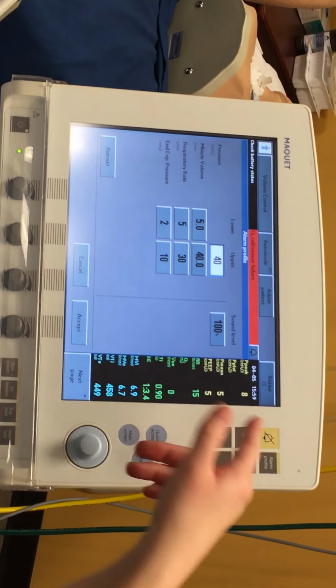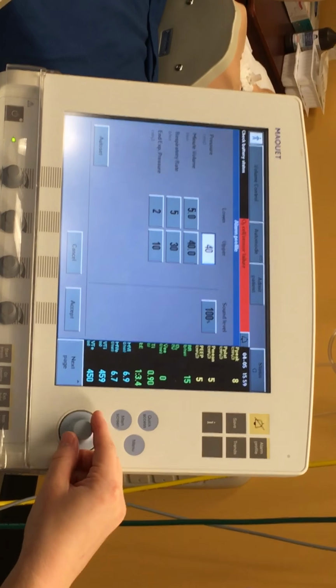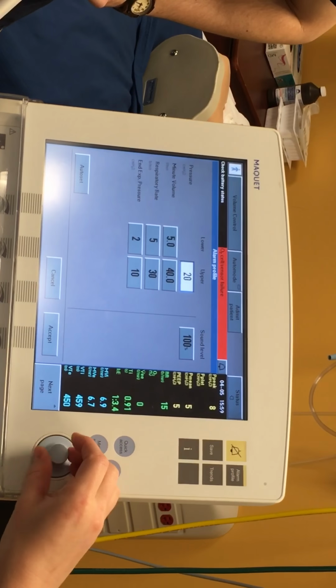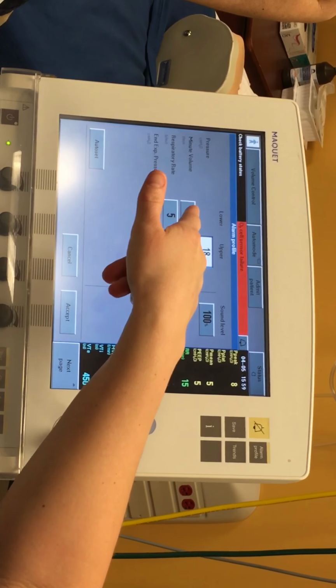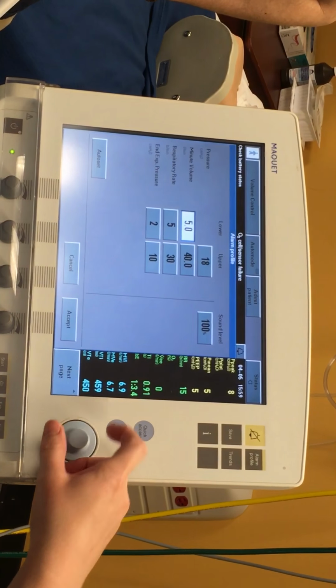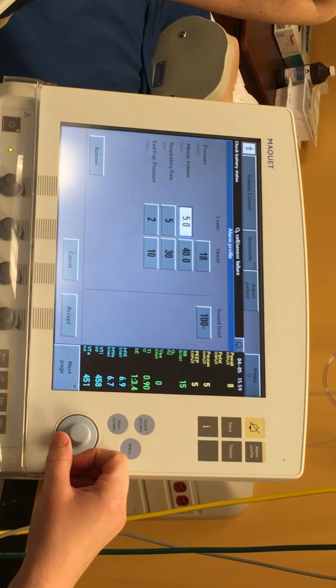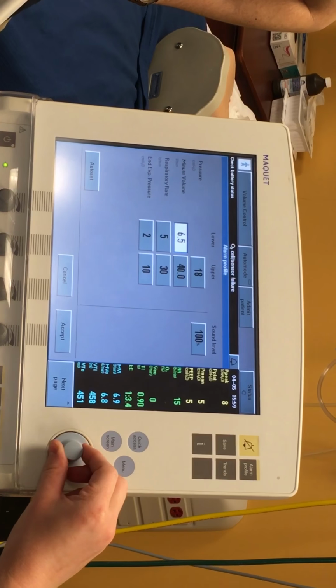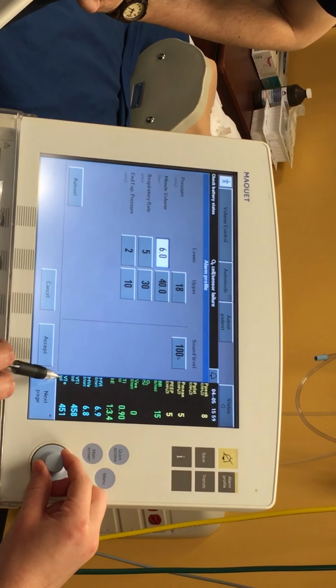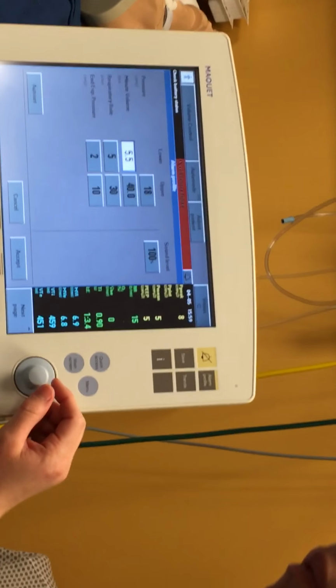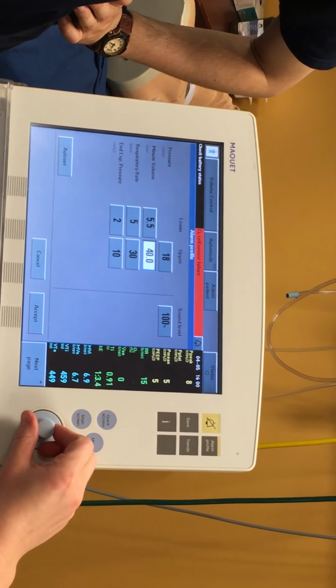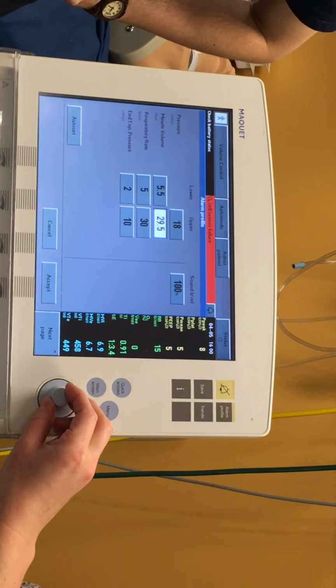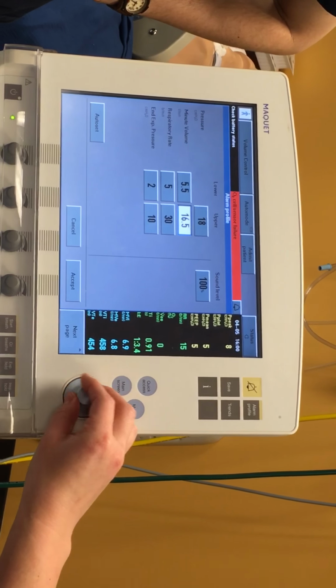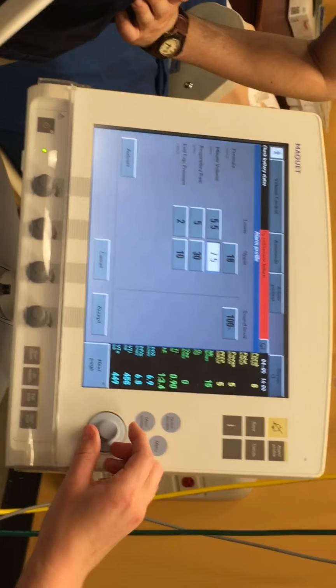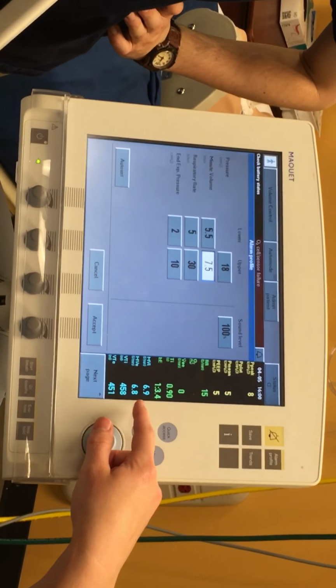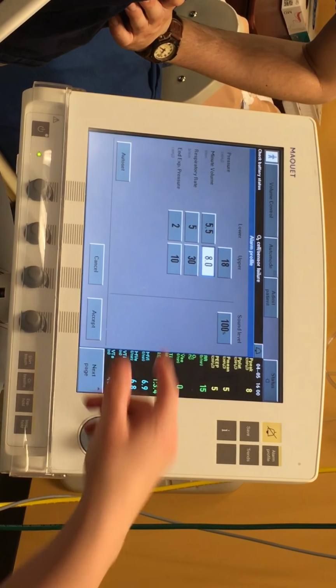Okay, so the alarm for pressure is going to be about 18. Your peak pressure is 8. Okay. So for minute volume, what's our minute volume there? 6.9. Okay, so I would go lower down and higher up. Now this is something you're going to have to adjust if your patient wakes up and starts breathing, because that's going to get added into the minute volume. So your high minute volume alarm will go off. So is 7.5 fine, or should I go to 8 if it's 6.9? I'd probably go to 8. Okay, it's not going to be a big deal.